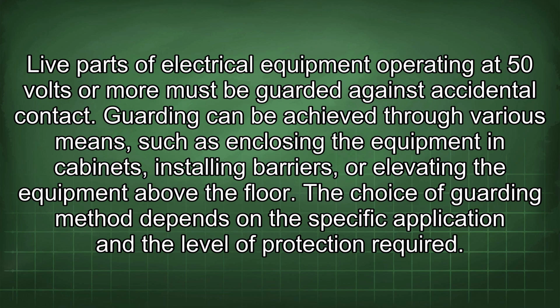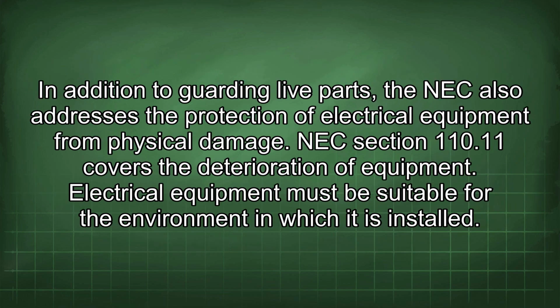The choice of guarding method depends on the specific application and the level of protection required. In addition to guarding live parts, the NEC also addresses the protection of electrical equipment from physical damage. NEC Section 110.11 covers the deterioration of equipment. Electrical equipment must be suitable for the environment in which it is installed.